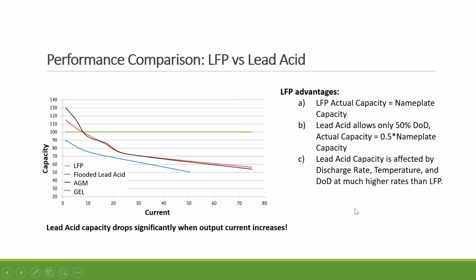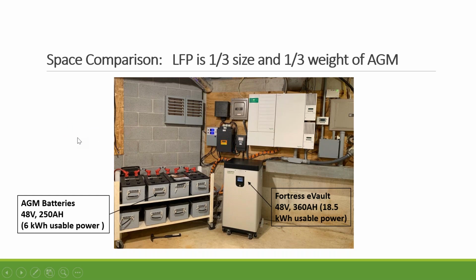And another interesting scenario is if you are living in the south and you need your air conditioning when the power goes off. Once you turn on that heavy load, the lead acid battery capacity is going to drop dramatically. So if you expect the battery to last for 2 hours, 30 minutes later the system shuts off. With lithium, as long as you're operating under the maximum discharging rate, the capacity is very consistent. So if it lasts 2 hours, it will last 2 hours.